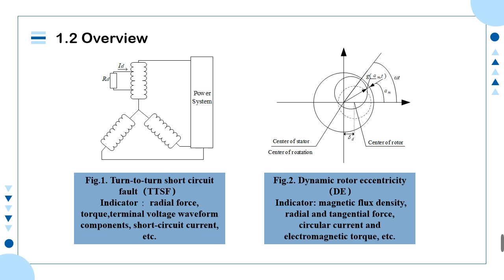There are two common types of faults in LSC: turn-to-turn short circuit in stator winding (TTSF) and dynamic rotor eccentricity (DE). Quantities of researches have been carried out on the single fault, but little literature explored the diagnostic criteria of their composite faults. Actually, these two faults usually happen in company.